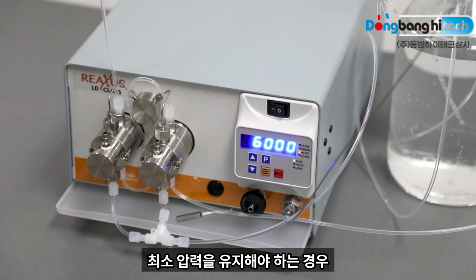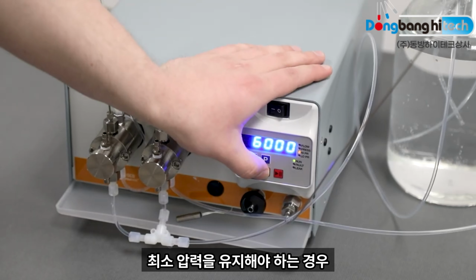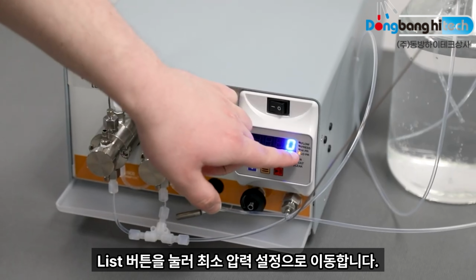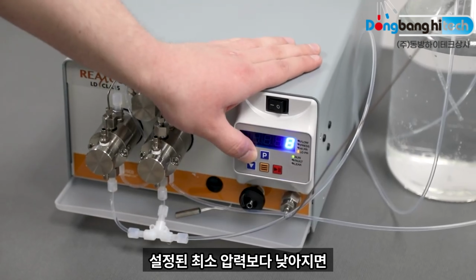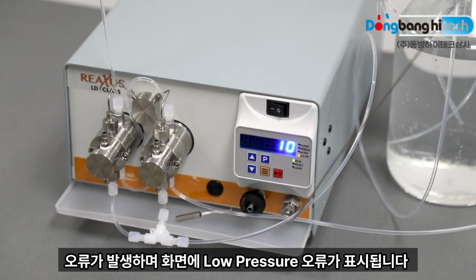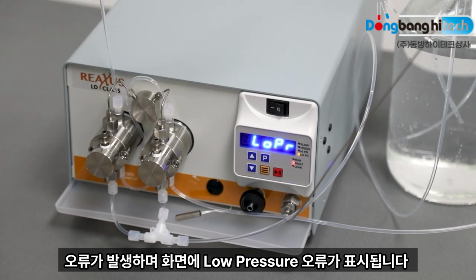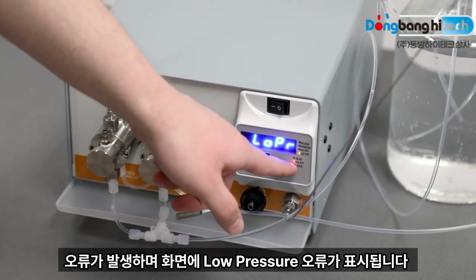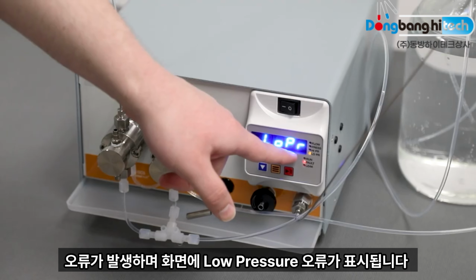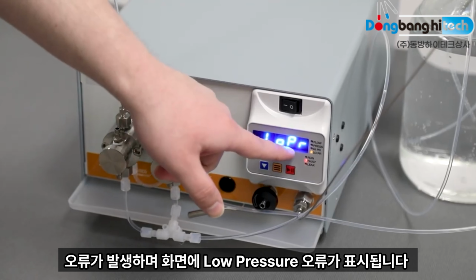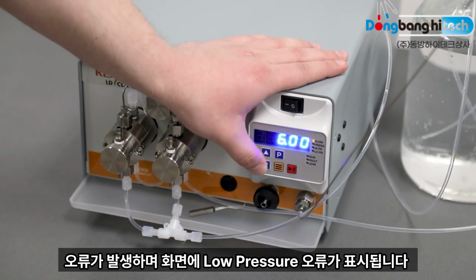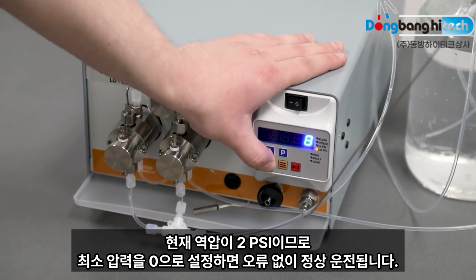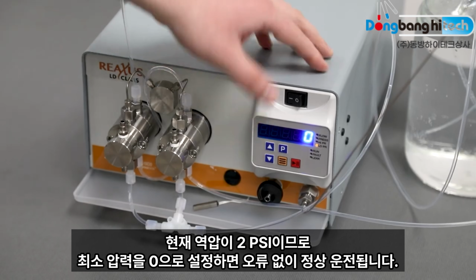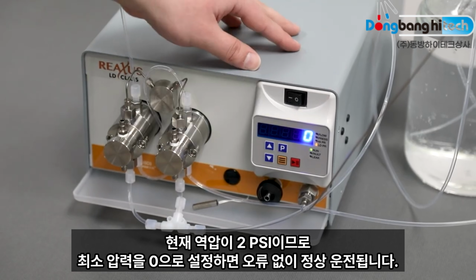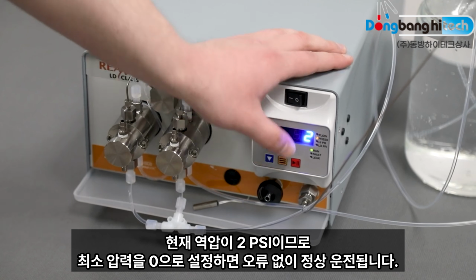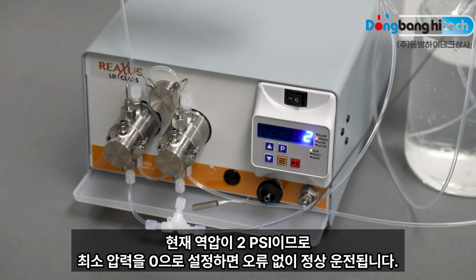In applications where you need to maintain a level above a minimum pressure, you'll press the list button again. We will go down to our low pressure setting, and I can increase my minimum pressure. After the pump has recognized that we are below the minimum pressure, you will get a fault and an on-screen indication of what the fault is. In this case, low pressure. If I want to clear that, because my back pressure is 2 psi, I will set that back to 0 and run. Still at 2 psi, I should not run into that fault.